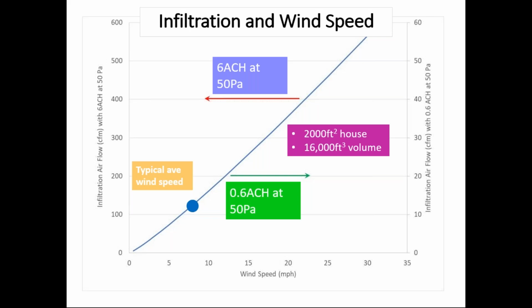A home with 3 ACH, a 2,000 square foot home, instead of having, say, 400 CFM of infiltration air when it's a 20, 25 mile per hour wind, would have about 200. If you drop down to passive house levels of 0.6 air changes per hour at 50 pascals, that would be 1/10 of the infiltration air. And if we look at what's a typical wind speed for most of North America, say 6, 7 miles per hour, we would be looking at about 120 cubic feet per minute of air blowing through your house with that wind speed at 6 ACH, and then maybe about 12 CFM with a much tighter sealed home.